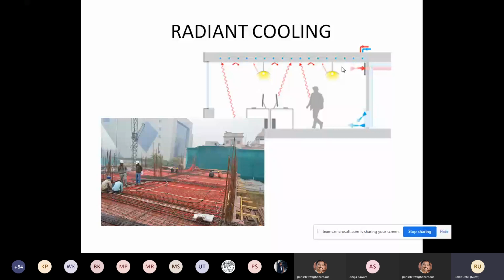Now, if this was such a wonderful thing, why is it not used so often, and why don't we hear about it? Because there are some restrictions to the system. As you all can see over here, there are no false ceilings. So all your ceiling elements, sprinkler pipes, lights, they will all be exposed. Many people don't prefer that kind of a look, and they would prefer to have false ceilings and all the lights and all the services hidden behind that. So that's one of the limitation factors of the radiant cooling.